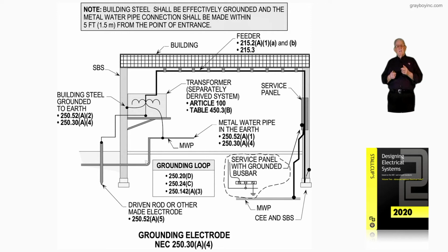And notice now in this section, 250.30(A)(4), the water pipe is mentioned first. And the reason for that, if it's not continuous as shown, and maybe spliced with PVC without putting a bonding jumper over it, it's not continuous. So they want you to check that out to see, does it need to be bonded in? If it's not continuous, it needs to be bonded in as well as the structural steel.